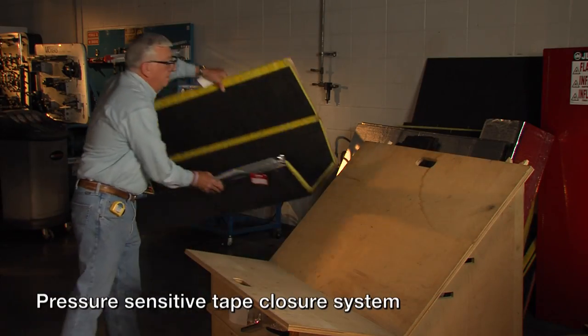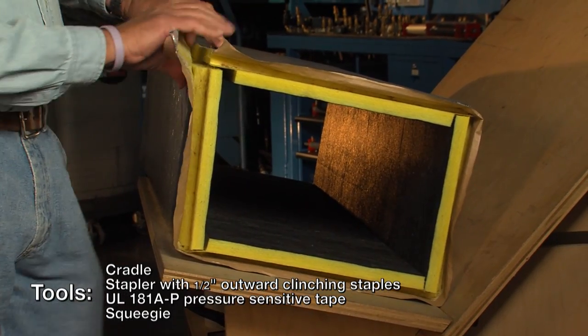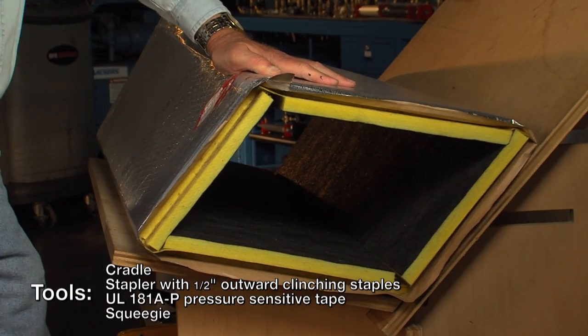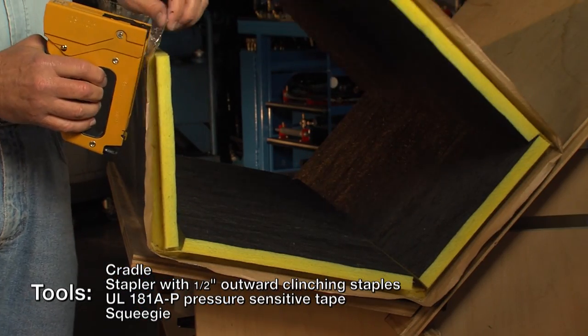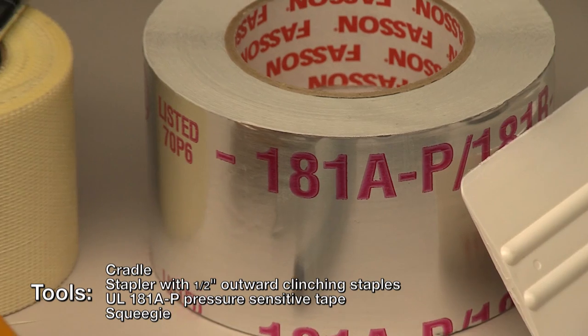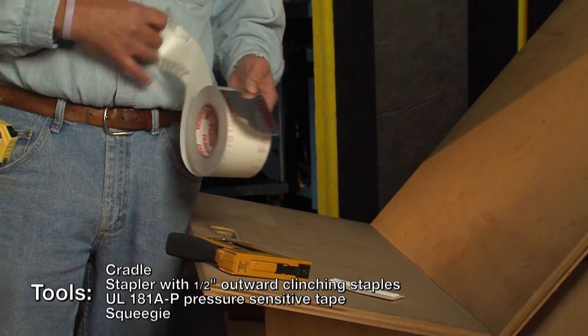To close a duct using the pressure-sensitive tape closure system, make sure you have these tools handy. A cradle that allows you to create a tight corner joint — the cradle is tilted about 120 degrees rather than 90 degrees, which allows you to get the right amount of tension in the facing so the corner closure is as tight as all the others. You will also need an outward-clinching stapler with 1/2-inch outward-clinching staples and a roll of UL 181 AP pressure-sensitive tape. Since we are working with 1.5-inch duct board, we recommend 3-inch wide pressure-sensitive tape.